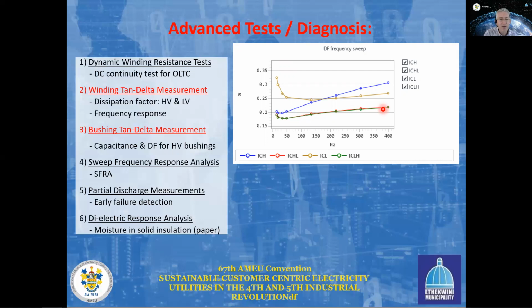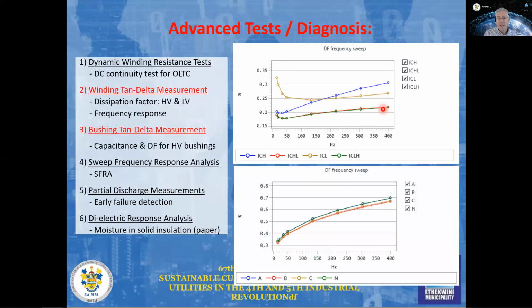Secondly, when we're looking at bushings, the same applies. We firstly look at the 50 Hertz measurement, which in this case here at 0.4% is a very healthy measurement. And again, for bushings, you cannot apply just one value. It really depends on the specific bushing that you're testing what level you apply and what you would fail. For oil impregnated paper bushings, again, the 0.5% limit is very much a good yardstick to use. So in this case here, we can pass this bushing without too many problems.